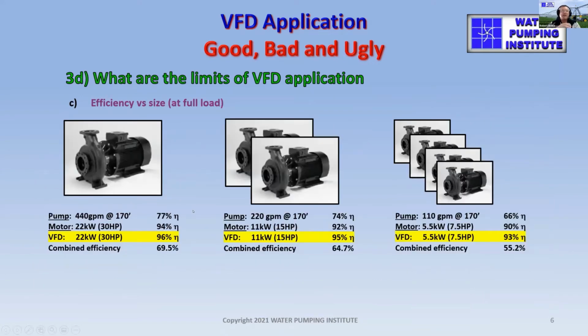Here's a bit of an indication. On the left, we're looking at a pump system, or 3 different pump systems: a single pump, a dual pump, and a quad pump. They're all delivering the same total volume at the same head, but the single pump has a much higher efficiency, the single motor has a much higher efficiency, and the single VFD has a much higher efficiency. You can see here I've highlighted the VFD efficiency in yellow.